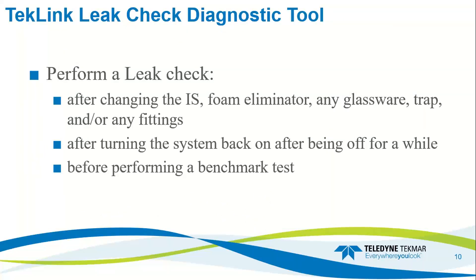Using TekLink's leak check diagnostic tool, you usually want to run a leak check after changing the internal standard, the foam eliminator if you use that, any glassware, the trap, if you loosen any fitting — basically any time you replace any part, you want to perform a leak check. After turning your system on after it being off for a while, maybe after the holiday break, you want to perform a leak check. And before performing a benchmark test, you definitely want to make sure that your system is leak-tight. If not, the benchmark might say that it has a failed purge valve when that might not be the case, and then you're going down the rabbit hole of trying to fix something that isn't broken.